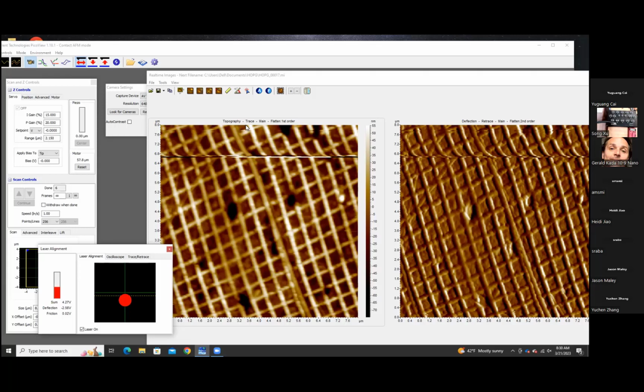So for those of you that are listening, it's important that you understand the breakout box needs to be connected directly to the front of the AFM controller. It should not be between the AC mode and head elect. It shouldn't be between the head elect and the microscope. It should be connected directly to the controller.